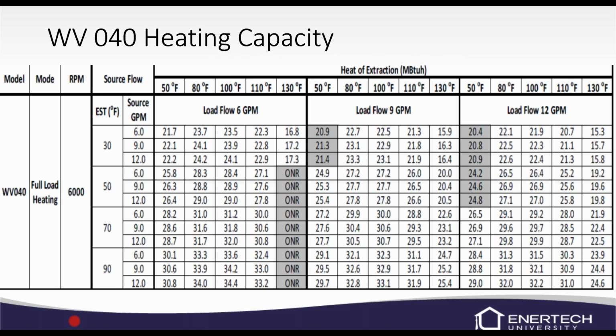Now, I wanted to show this little chart here. Let's say this WV040, it's a 3.5 ton unit, but as entering source temperatures go down, obviously we're going to lose capacity. So you've got to take that into consideration. The most that this VO40 can do is 3.5 tons, so make sure we're not trying to overload the unit with too much load on it.